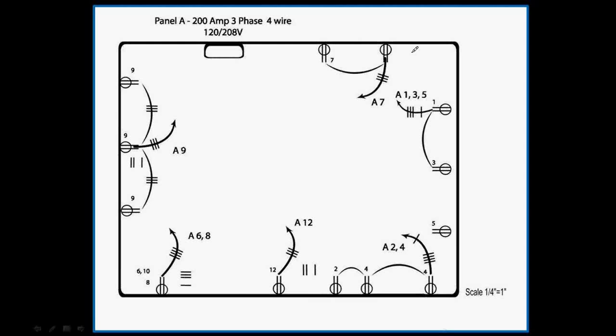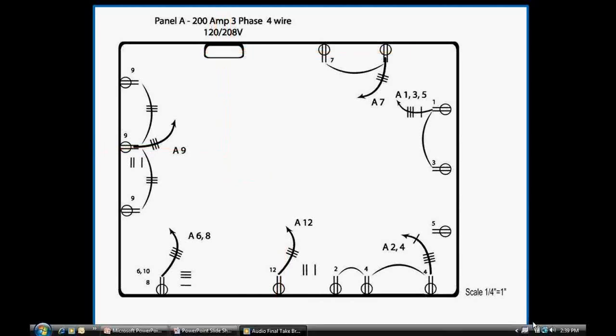Notice that I over-roll slightly to cover the length of conduit riser, which is the conduit going up or down from the outlets or panel. Also, notice how I roll over the path of the conduit at a right angle. I do not need to take off couplings, connectors, or supports. Red Rhino will add those materials for us.